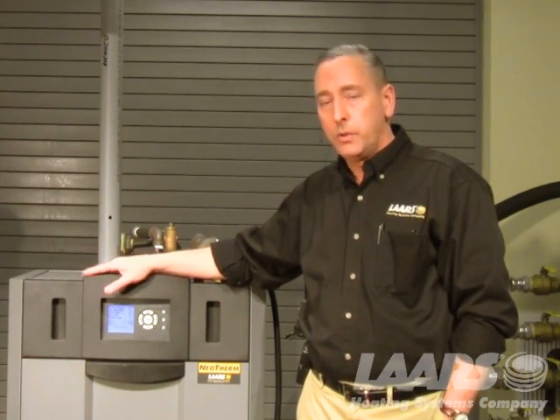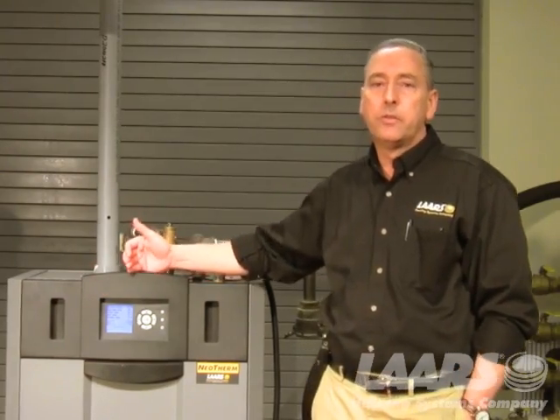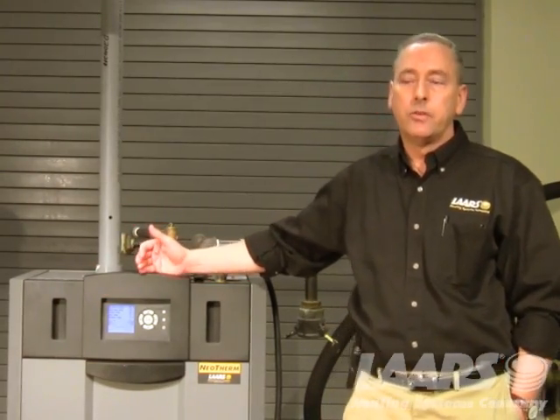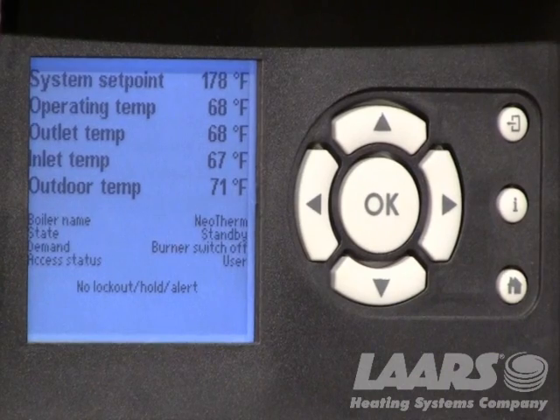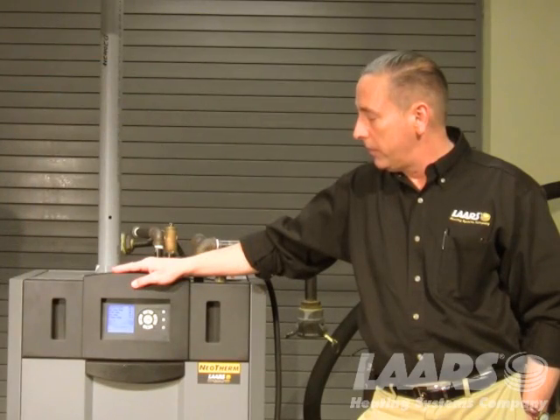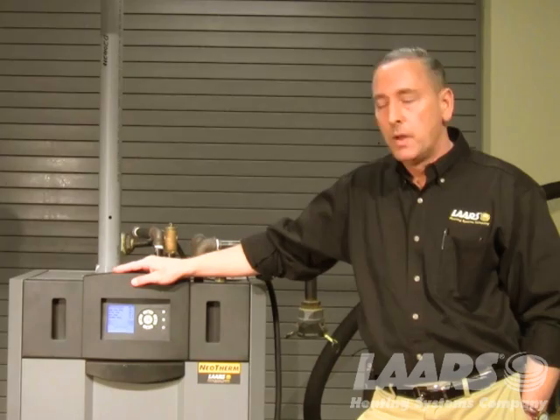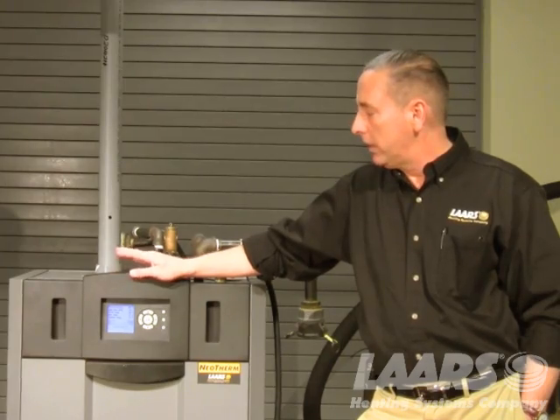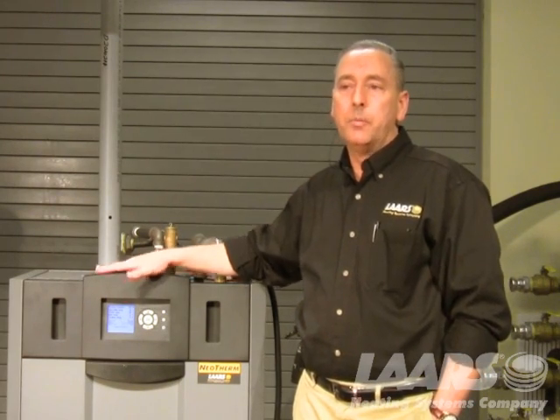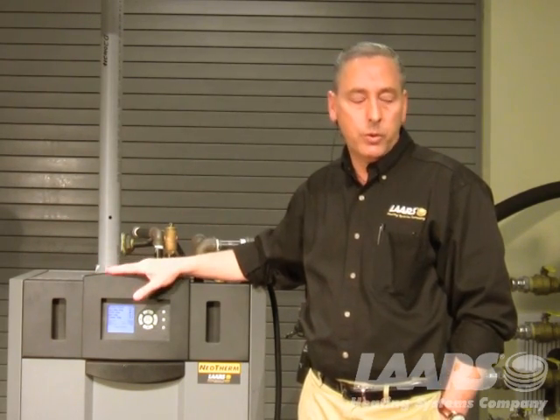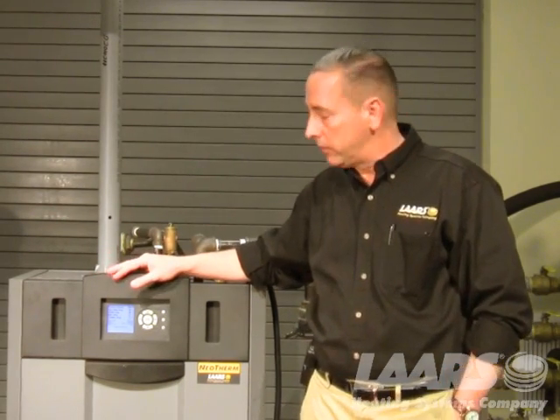When you do cascading, you have a system sensor and an outdoor sensor. Those are provided for you, so you will need to wire those into the control system, and then we'll be able to go in and program each boiler. We're going to start off with the master control, show you how to program it, and then get into programming the lag boilers or slave controls.